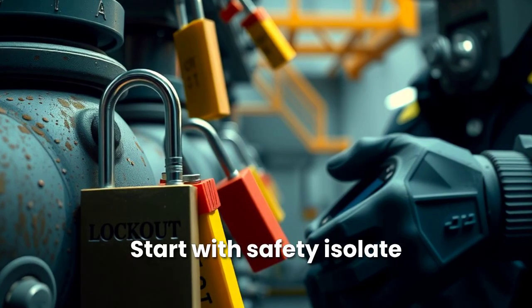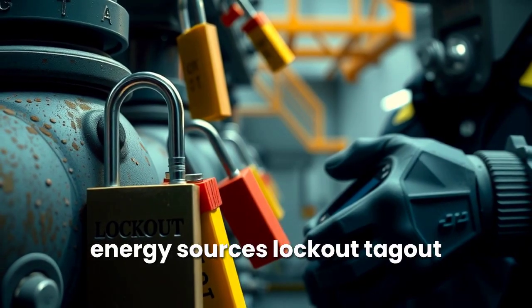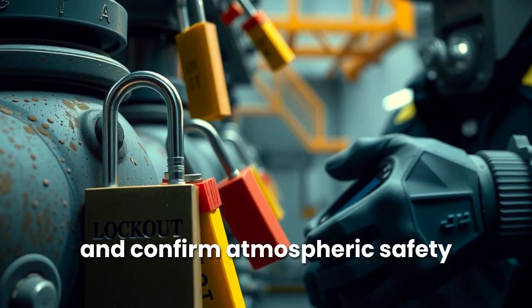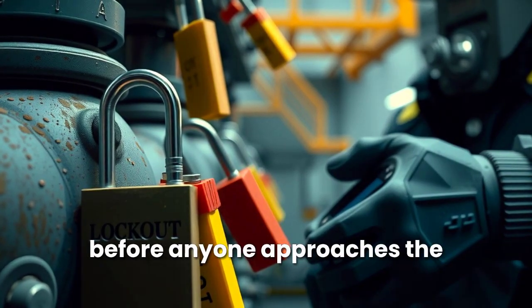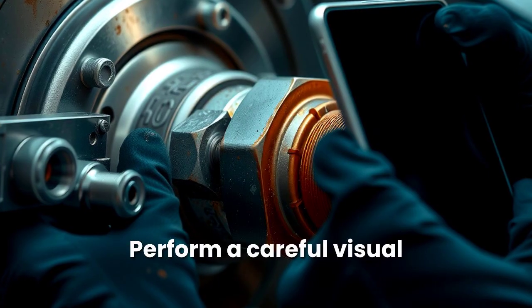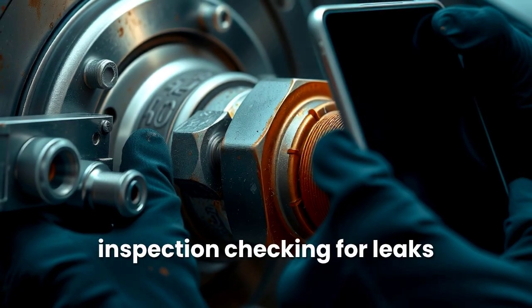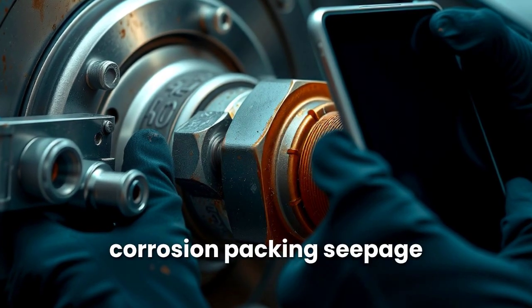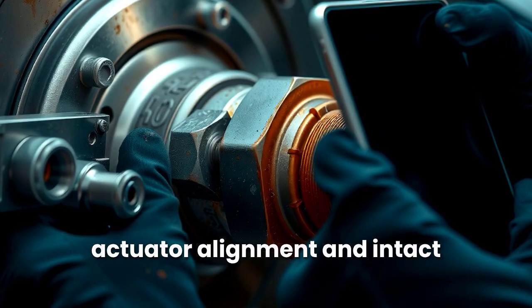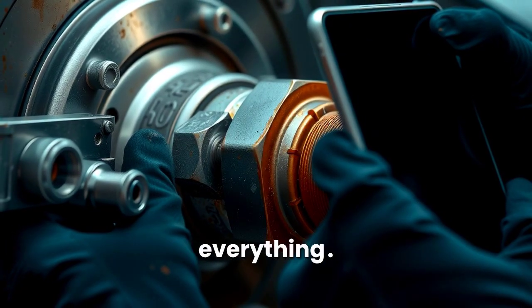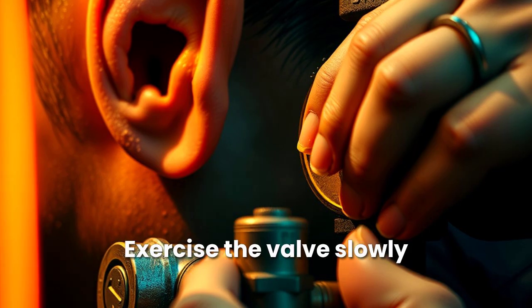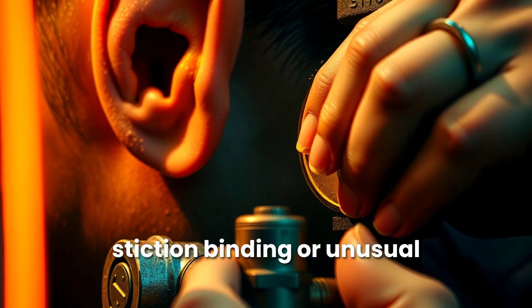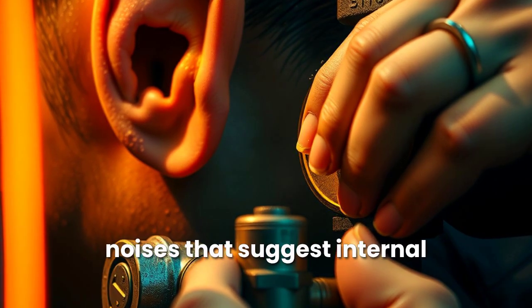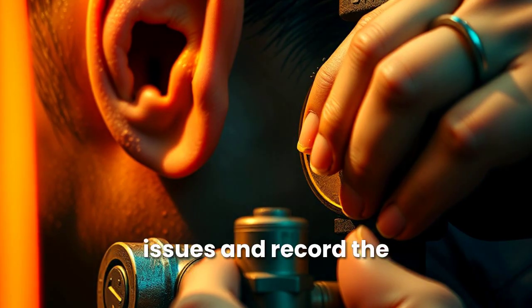Start with safety: isolate energy sources, lockout, tag out, and confirm atmospheric safety before anyone approaches the valve. Perform a careful visual inspection, checking for leaks, corrosion, packing seepage, actuator alignment, and intact fasteners while documenting everything. Exercise the valve slowly through its range, note stiction, binding, or unusual noises that suggest internal issues, and record the symptoms.